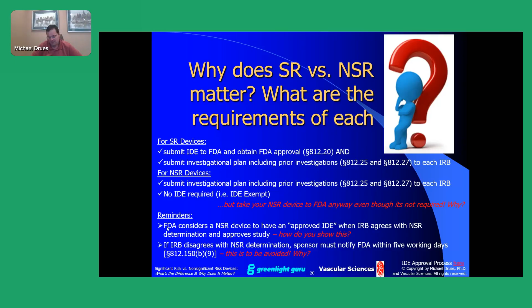Next question. If the device is SR, what do I do? Or alternatively, if it's NSR, what do I do? So just to recap, because I know this is a little confusing to some of you, if your device is SR, you notify the FDA via an IDE, and you also need to notify all of the necessary IRBs. If, on the other hand, your device is NSR, you're not required to notify the FDA. In other words, you're IDE exempt, although, as I said a moment ago, in most cases I still strongly recommend to my customers to notify them anyway, for reasons that we'll talk about further in a couple of minutes. But you still have to notify all of your IRBs. So at the end of the day, you always have to notify the IRBs. That goes without saying. The only question is, are you required to notify the FDA or not? And if so, are you required to submit an IDE, or are you IDE exempt?